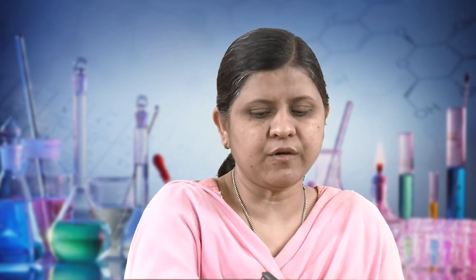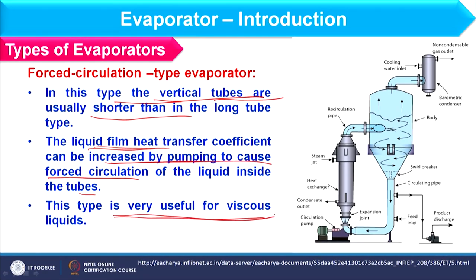The forced circulation evaporator is used specifically for fouling-tendency liquids and viscous liquids that cannot recirculate on their own. Vertical tubes are arranged and a pump causes forced circulation of the liquid inside the tubes, increasing the liquid film heat transfer coefficient. This type is used for viscous liquids.